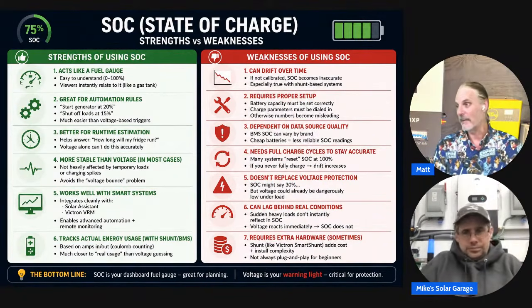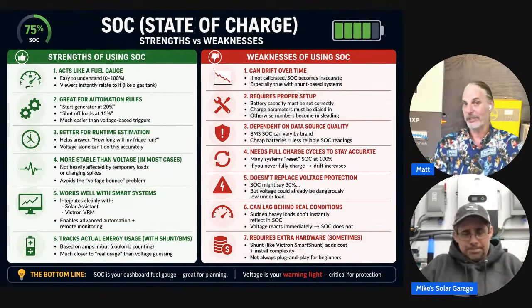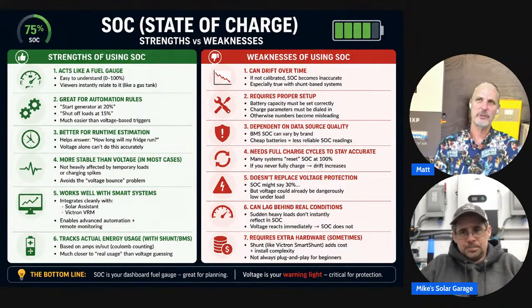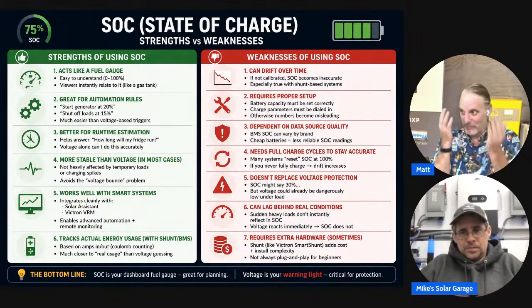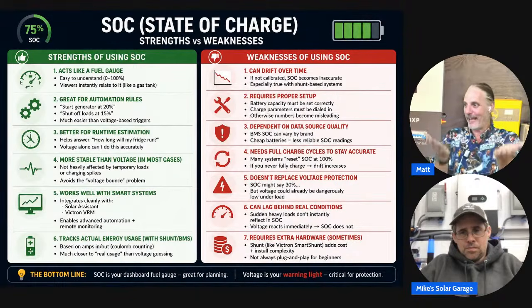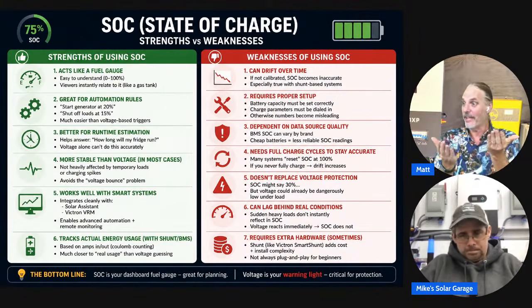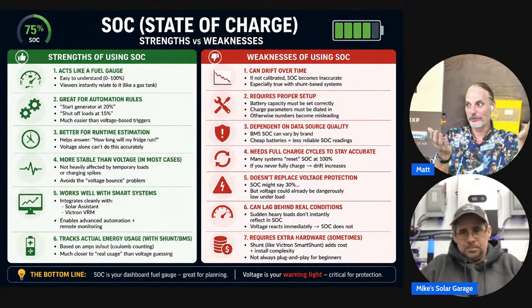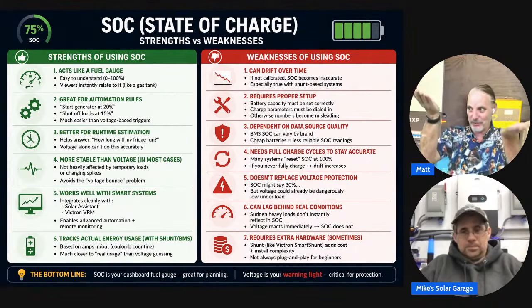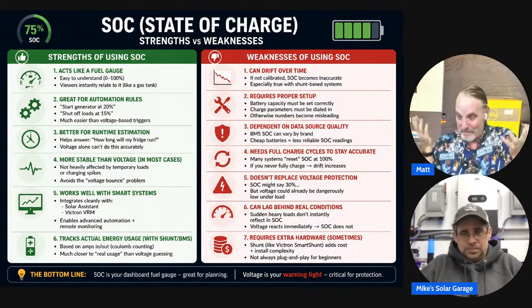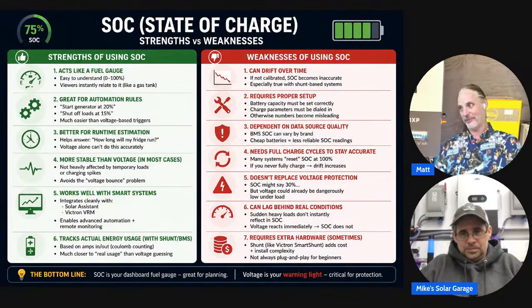So it probably had bricked, or could have, but it came back on. Fortunately it came back on. I'm not sure, to be honest, if it could have been shut. All I know is that when it gets that big of a variance, the gap gets worse and worse when those shunts aren't accurate enough. This one continues to lose voltage and these continue to gain state of charge. That's a big, big difference you're talking about.